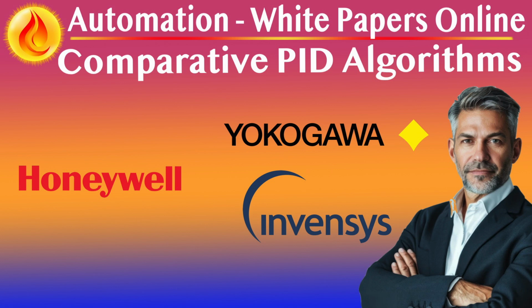Proportional, integral, and reset behavior. Honeywell's PID logic is engineered for clarity and simplicity. Gain and proportional band are clearly linked. Integral action is consistent across modes. Anti-reset wind-up, ARW, and external reset feedback are seamlessly built into the PID blocks. Reset logic accommodates mode transitions, saturation events, and setpoint handovers without requiring auxiliary logic.